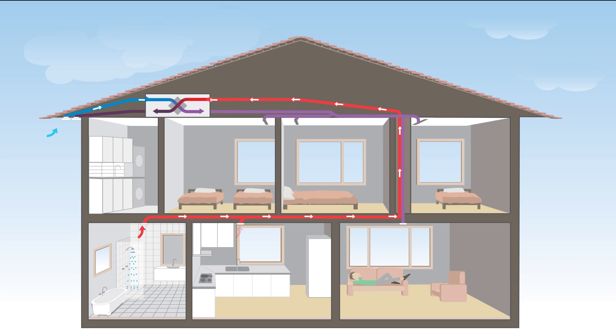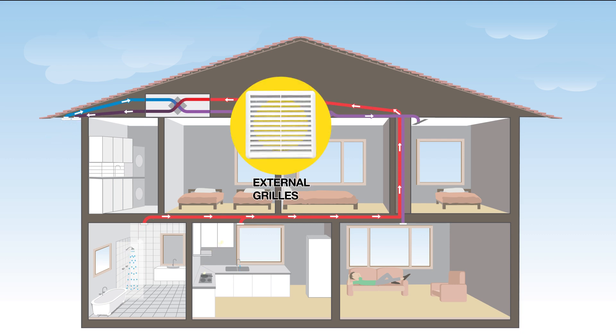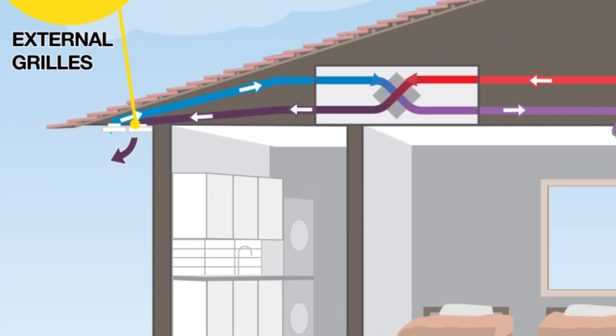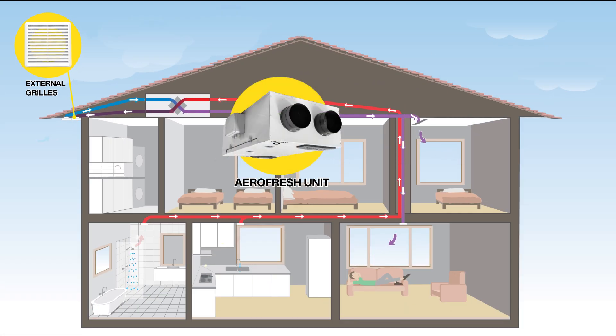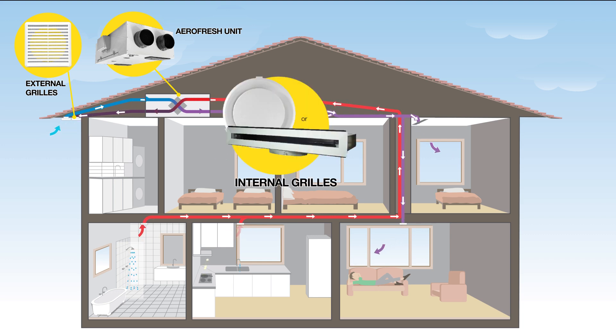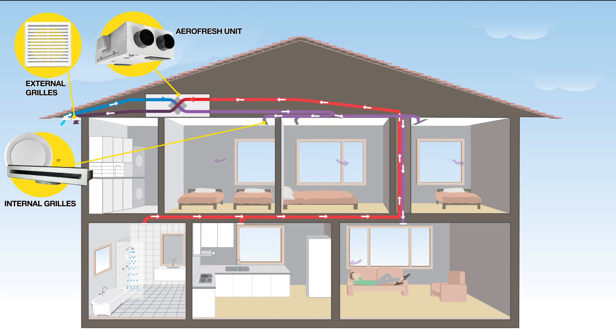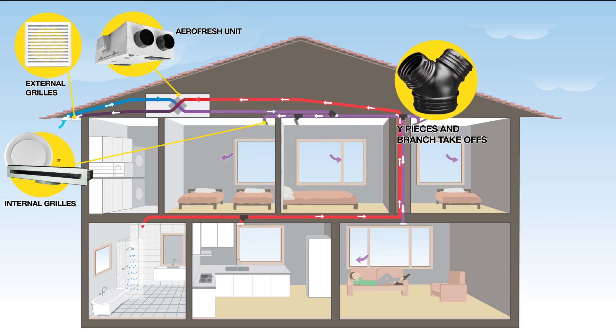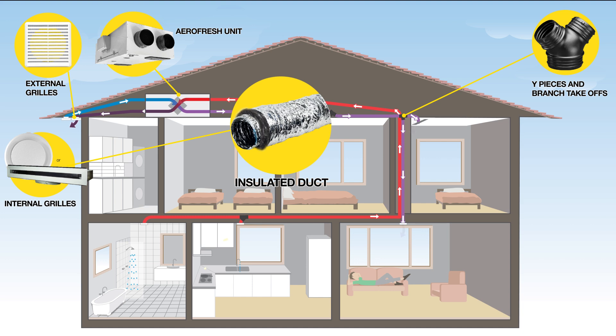A well planned installation is a lot simpler than you may expect and utilises familiar products like external grills, which are installed at least one and a half metres apart. Internal supply grills are installed to provide fresh air into habitable rooms such as living spaces and bedrooms. Y pieces and branch take-offs connect insulated duct together from different rooms.